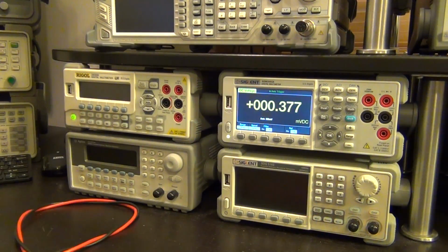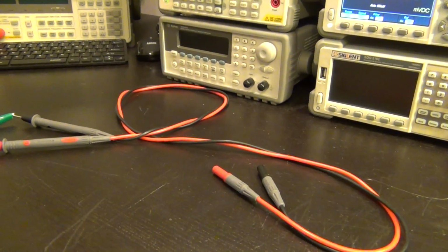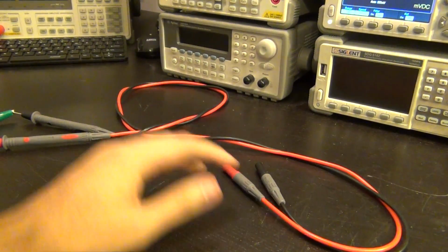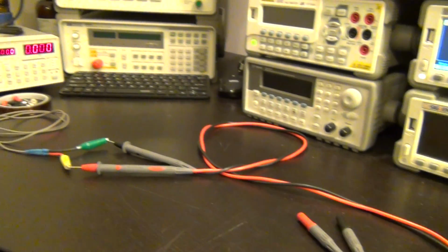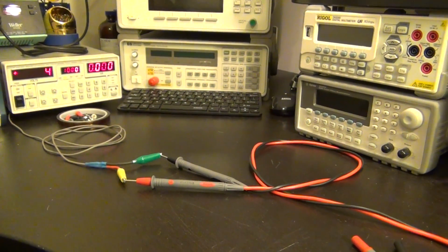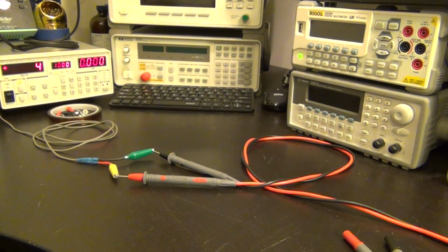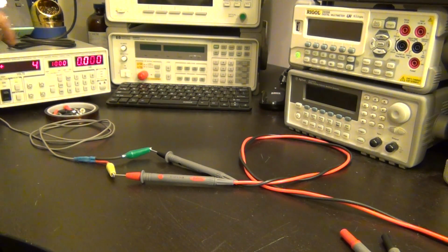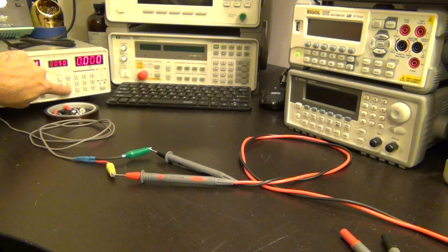Under this condition, the cable is completely exposed. The two ends are open and wrapped together, and I'm going to set the input to 5000 volts just to see if the cable will break down. We're going to set this to 5000 volts and enter.